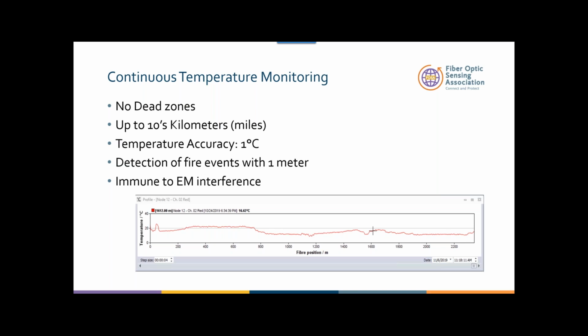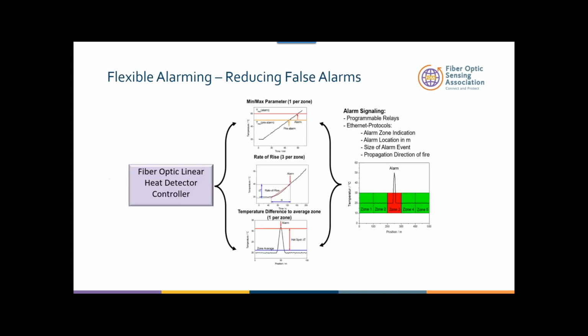It will be installed in areas such as cable trays. If you literally use a fiber optic cable that has metal wires in it, that can actually induce more current. So the ability to have this sensing system, in comparison to the conventional systems where they have wire and it's active, in this case, it's a very passive sensor.